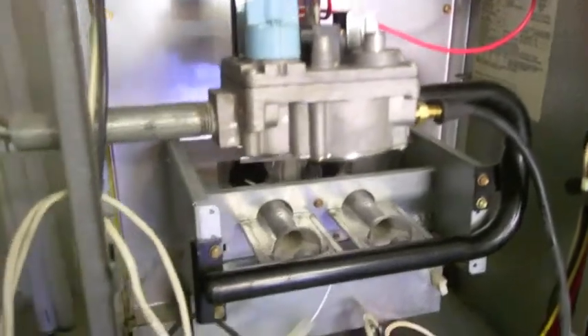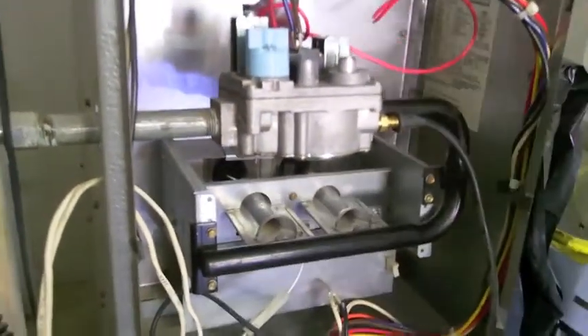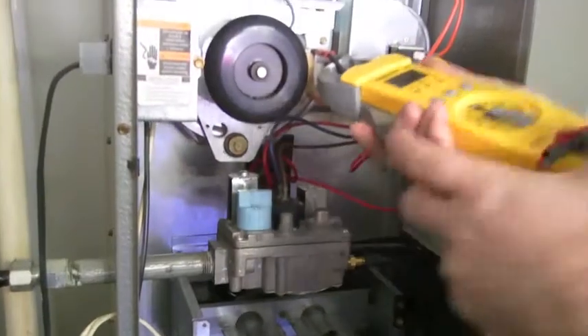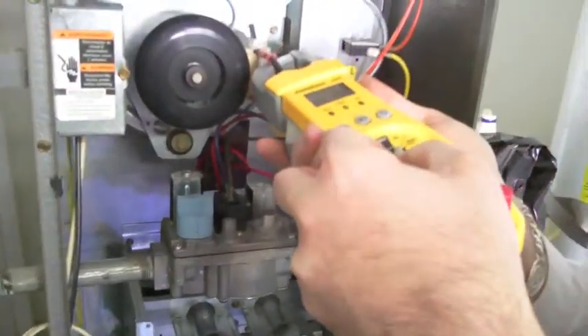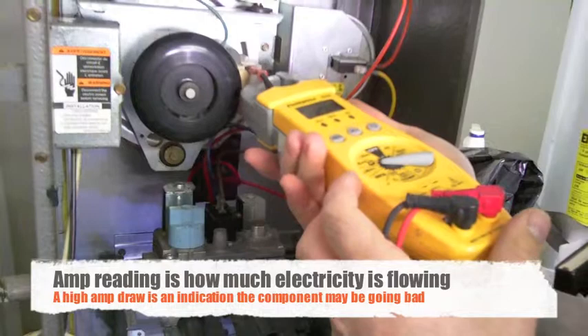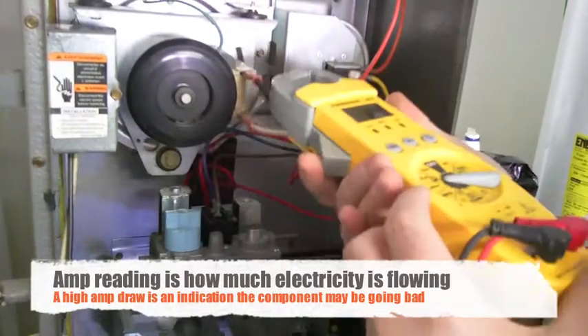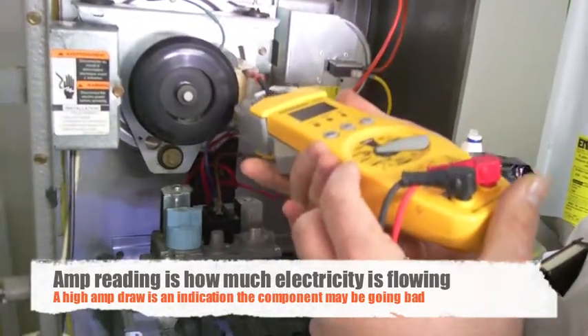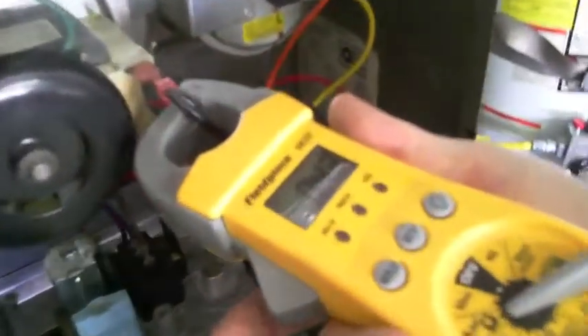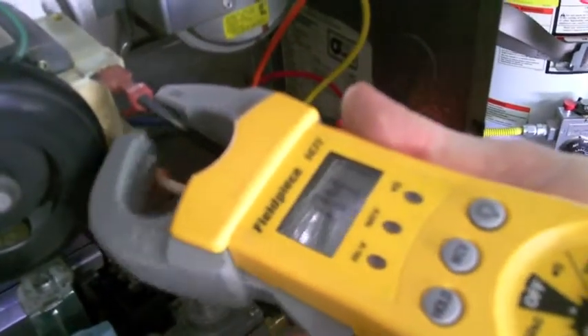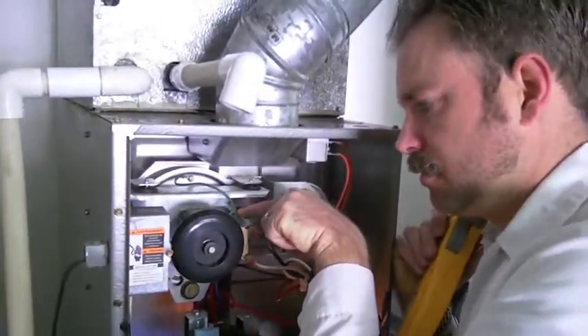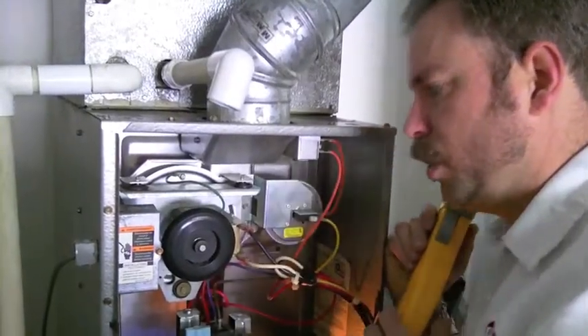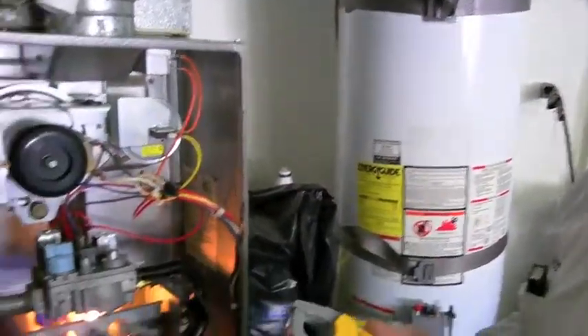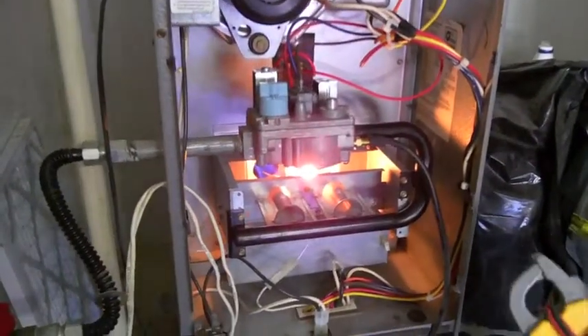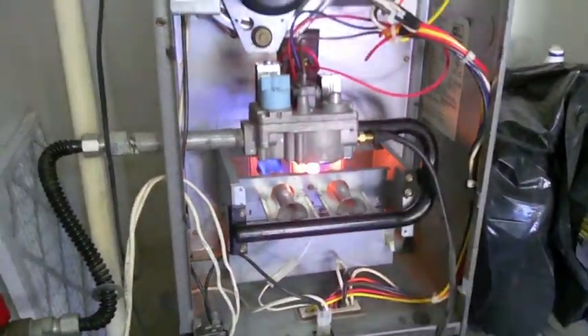Okay, now our inducer draft motor is starting, and we can test the amp draw on this, which is 0.43, 0.41, and the tag right here will tell you what the range is, and it should be 1.84 on the high side, so we're well within range on that. Now our flames are starting. Our igniter went.